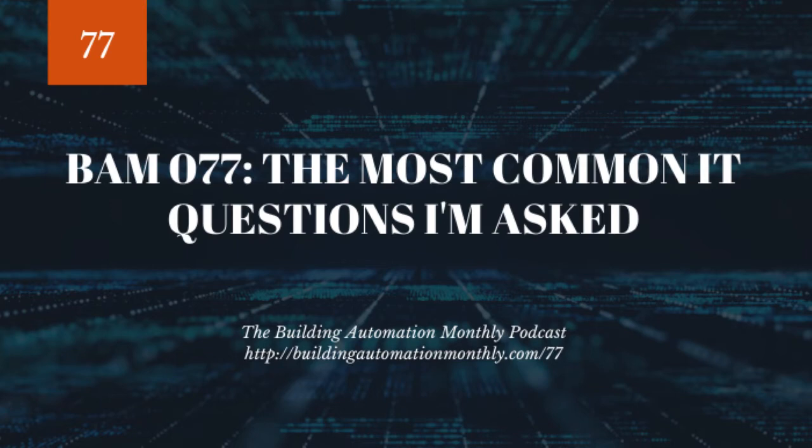My answer was, well, it depends on the environment. If you're on a VLAN and you're segmented from all other traffic, and this isn't a super secure site, and you're not riding over public Wi-Fi, then you probably don't need HTTPS for your Fox protocol. You're probably good with HTTP, because if someone's into your internal network and then on your BAS network, you've got bigger issues than them sniffing your Fox protocol and saying, oh, look what I see. You've got issues that they're on your freaking network.